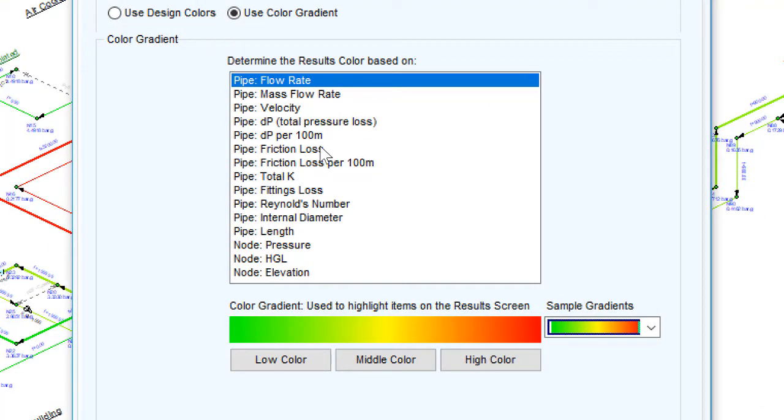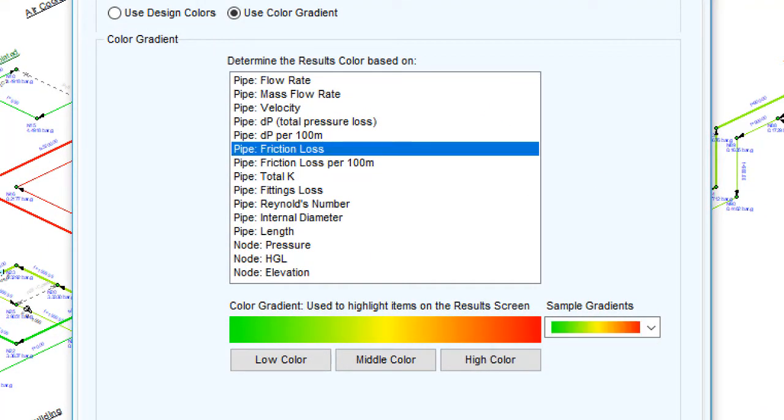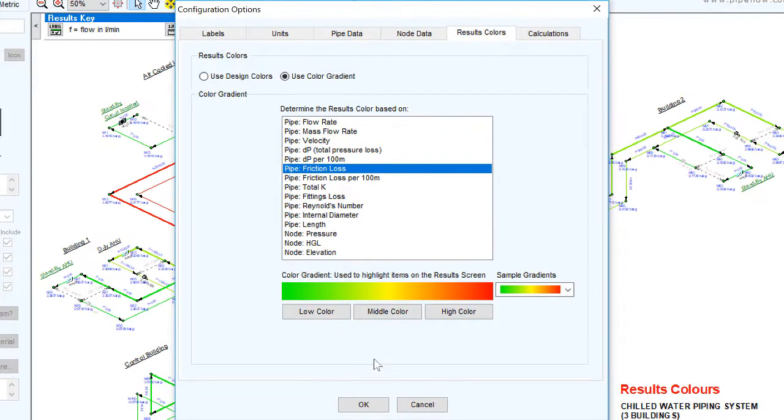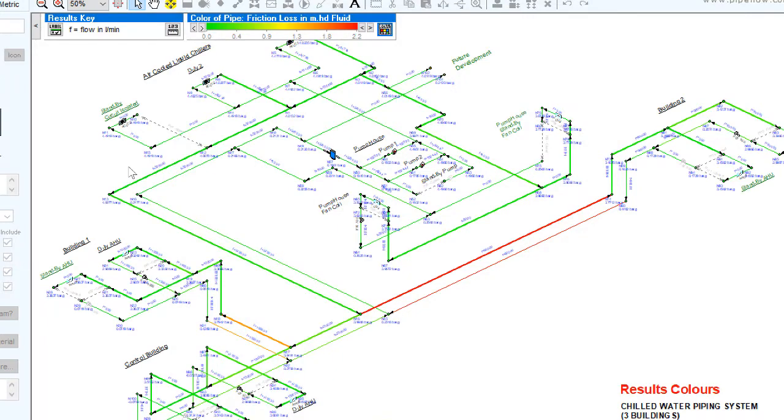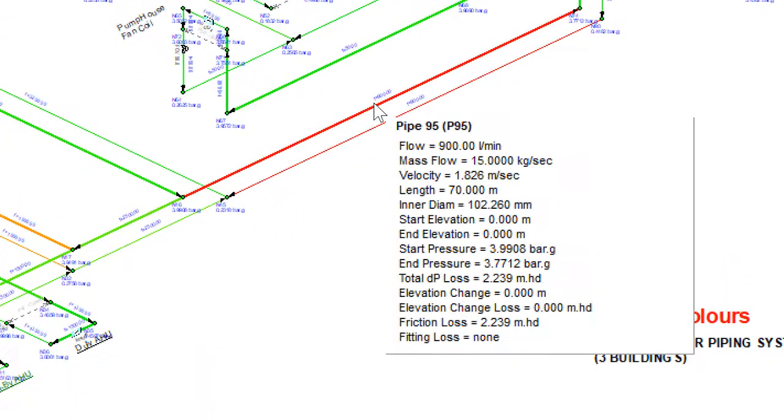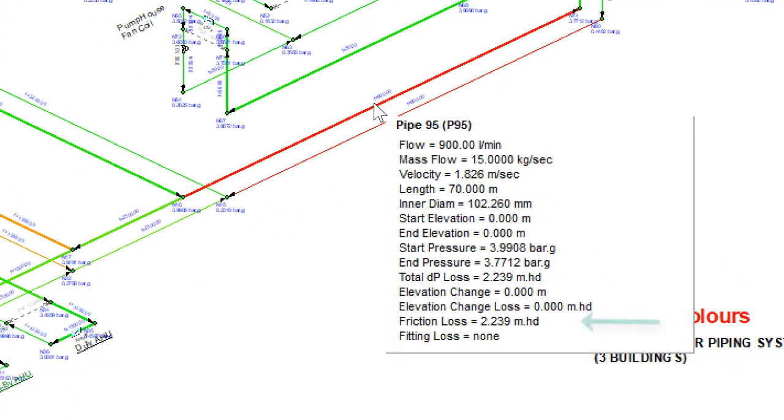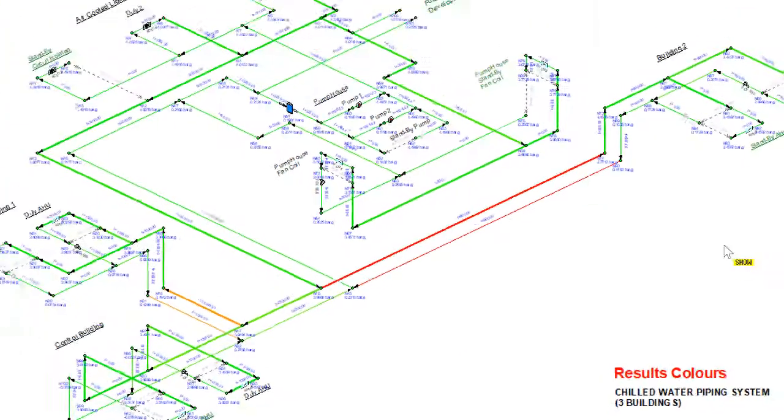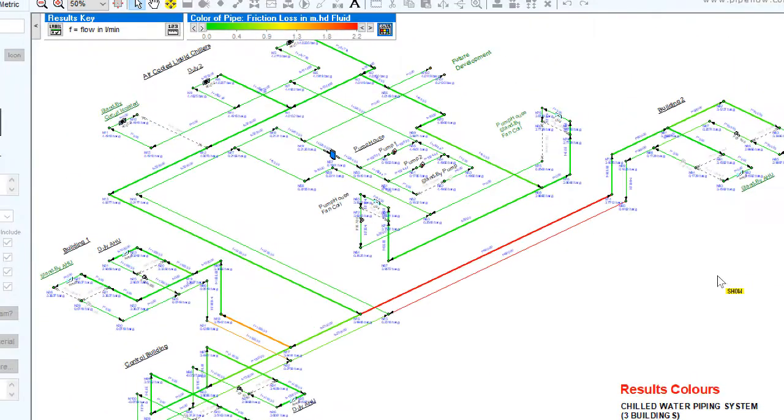Select a calculation category to be displayed on the colour results screen. You might want to look at where the highest friction loss occurs. Click OK to update the drawing plane. Looking at the colour code, we can easily pinpoint the pipes with the highest friction loss. However, this may be down to the length of the pipe.